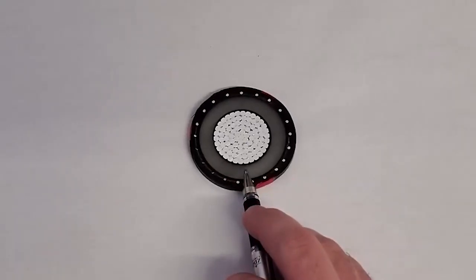So the insulation here, this white, is XLPE. They have a lot of different types of insulation. Another popular one is EPR. That's kind of orangish looking, sometimes almost red looking. And this XLPE. There's also paper insulation. You can use oil, but these are the most common, EPR and XLPE.